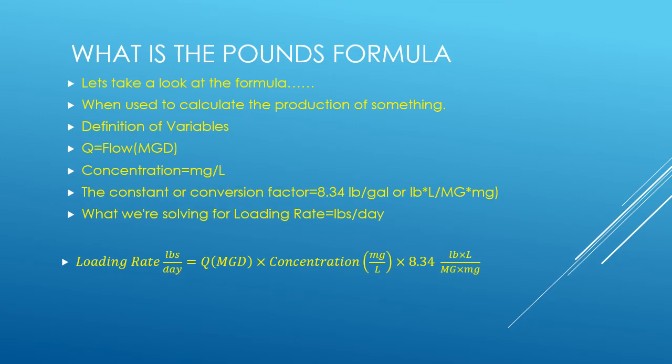Let's take a look at the formula. This is used to calculate the loading rate of a product in pounds per day. Let's look at the variables: Q, which is equal to flow in MGD; concentration, which equals milligrams per liter; and the constant, which is 8.34.